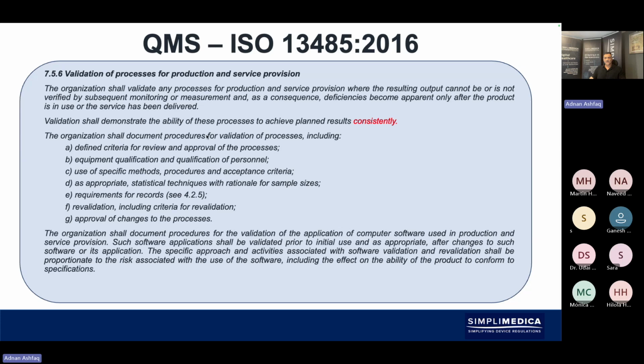Validation shall demonstrate the ability of these processes to achieve planned results consistently. So that's been highlighted in red for a purpose, because it's not to look at validation or results that are meeting predetermined requirements as a one-off. It's looking at consistency. Then the standard goes on to state that the organization shall document procedures for validation of processes, including the following: defined criteria, equipment qualification, the qualification of the personnel, resources, use of specific methods, procedures and acceptance criteria, as appropriate statistical techniques with rationale for sample sizes. So as I said, in the coming weeks and months, we will be exploring that also. Requirements for records, revalidation and approval for changes.